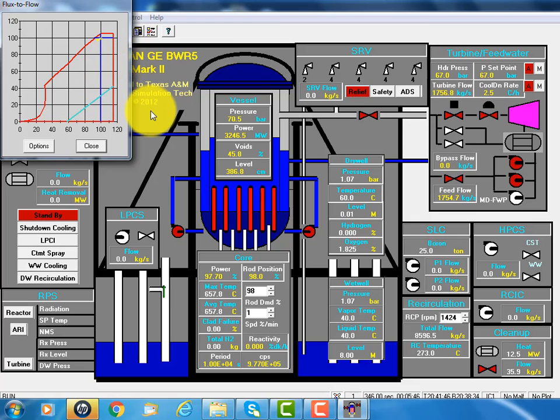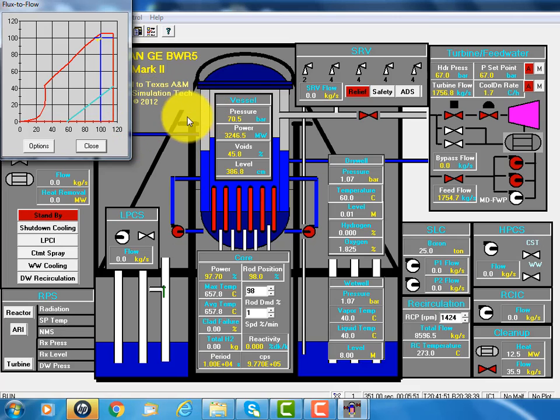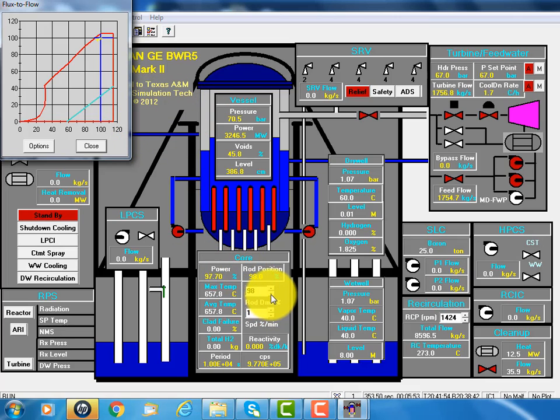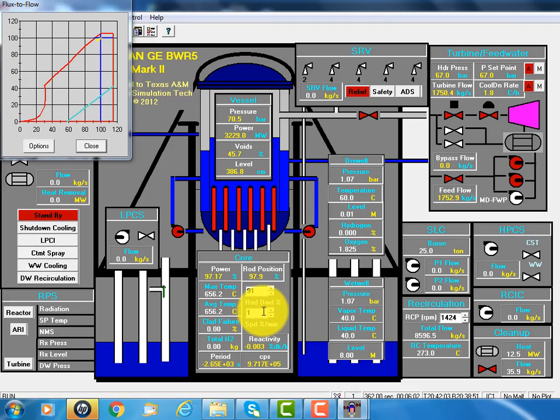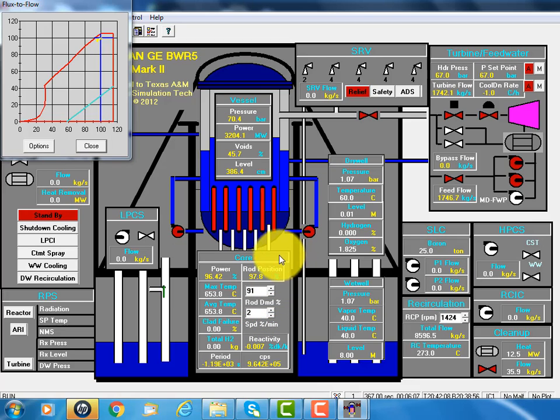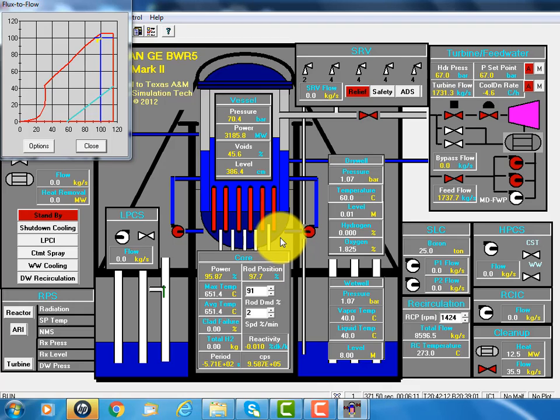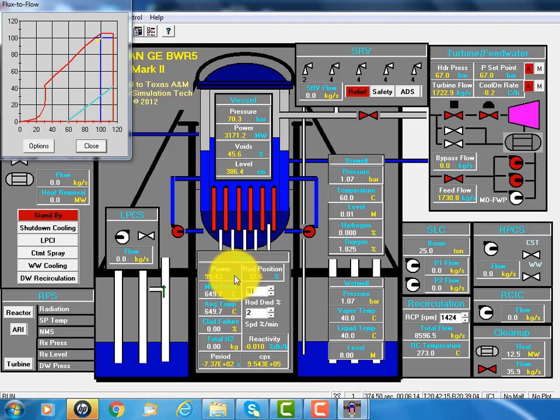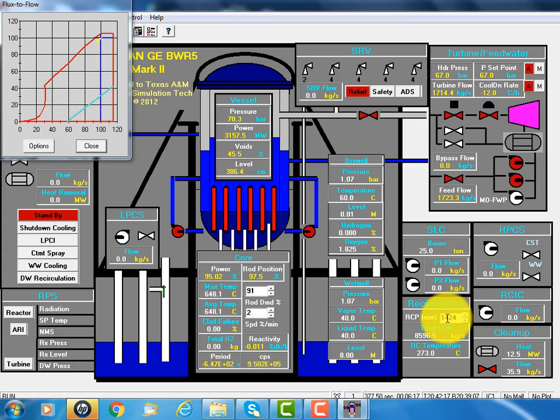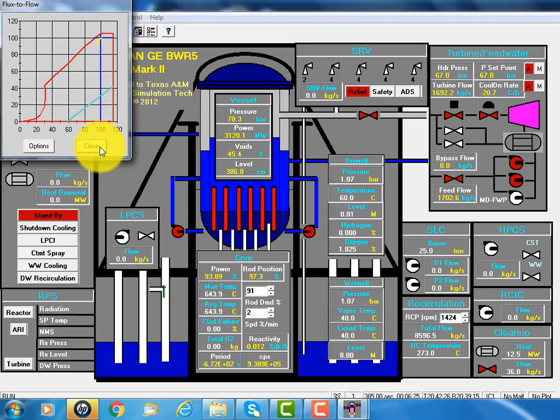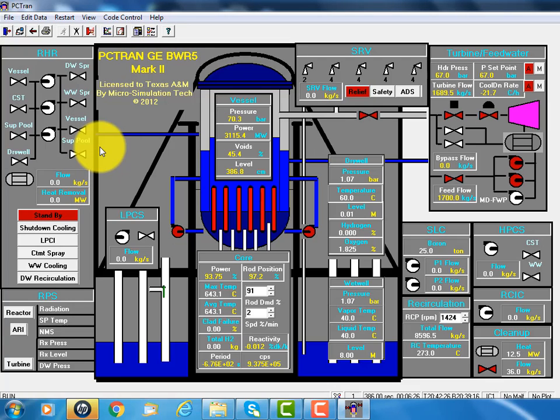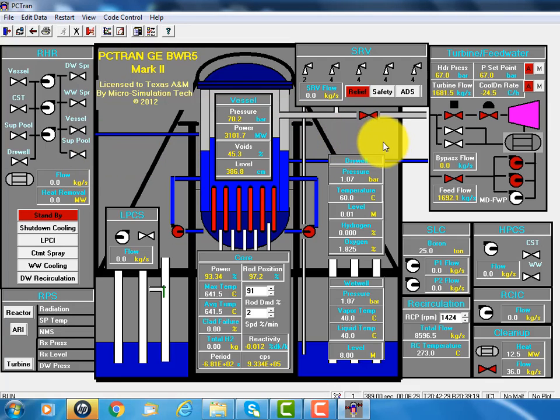And control of the flow is not the only way to adjust the power. We can also insert the rods. Target originally is 98%. Suppose I reduce it to 91%. And here's the rod speed. You see, the rods will move in. You see, they slowly move in, and the power goes down. Since we do not change the flow this time, so the power will go down vertically in this diagram. So let's close the diagram. And that's just the normal operation.